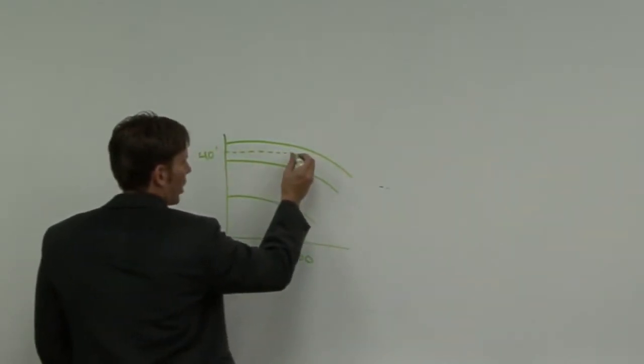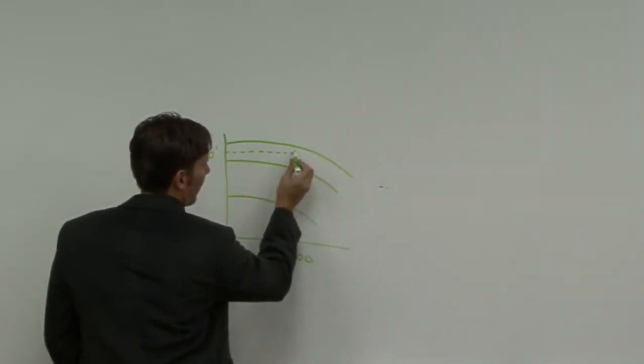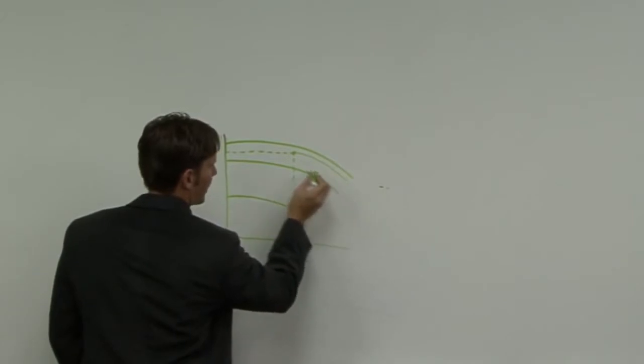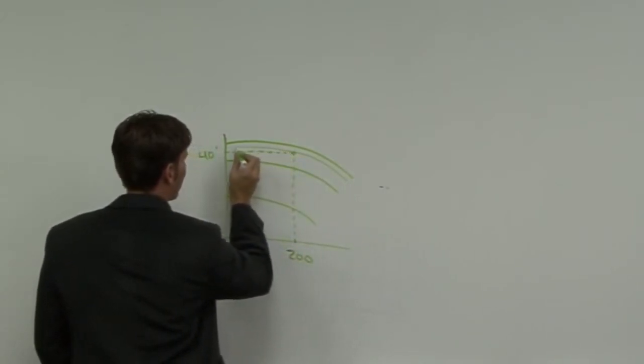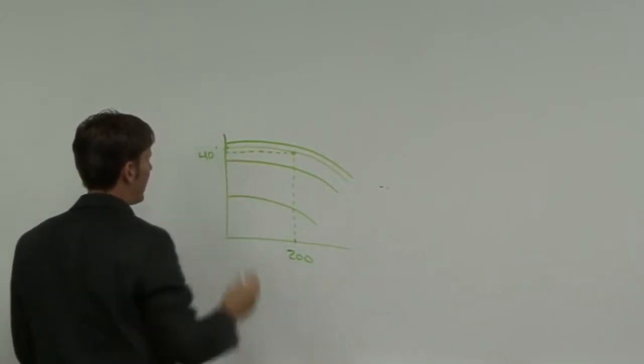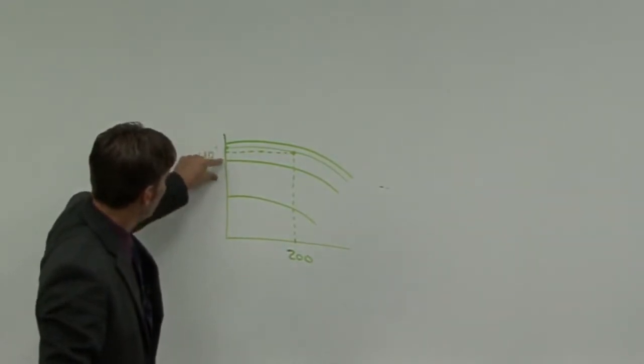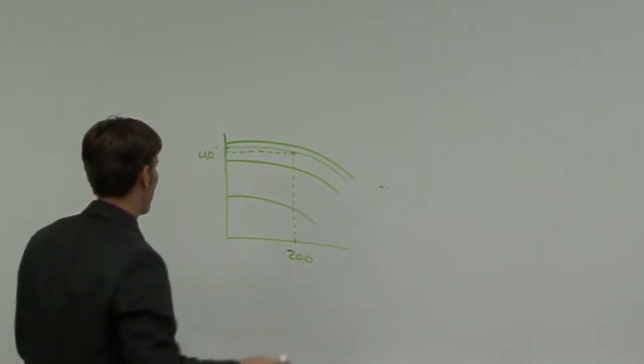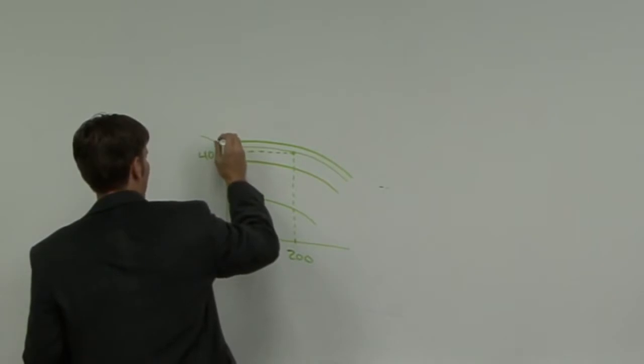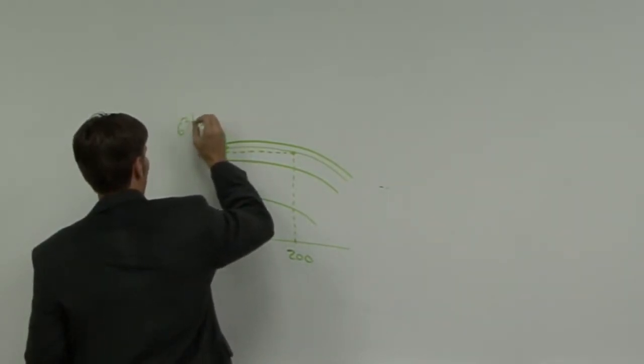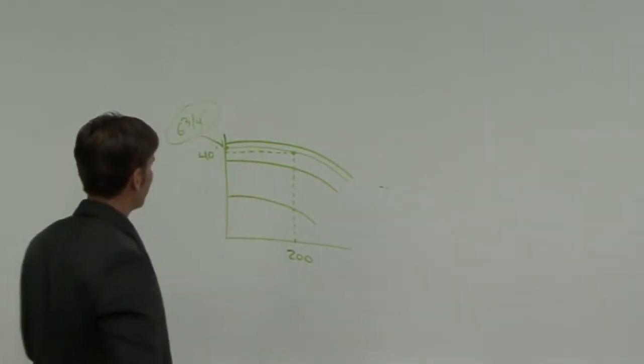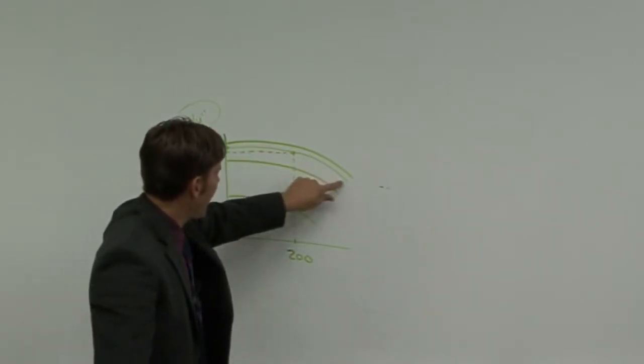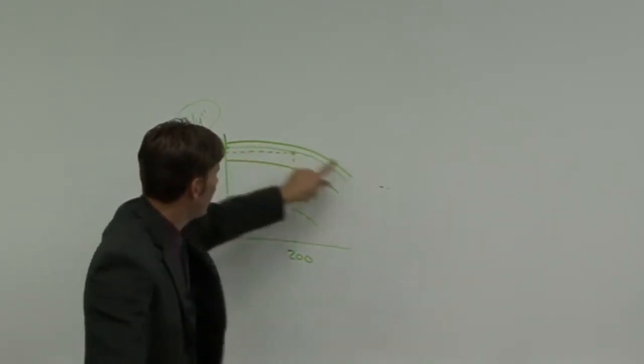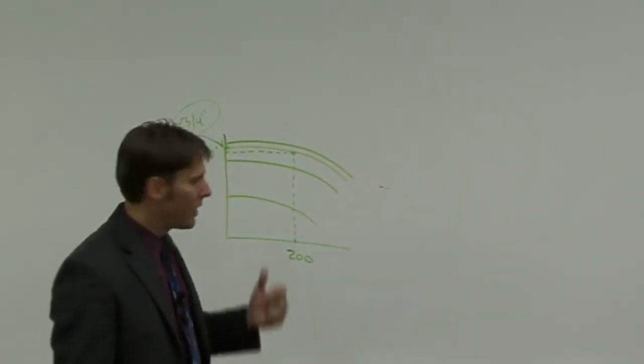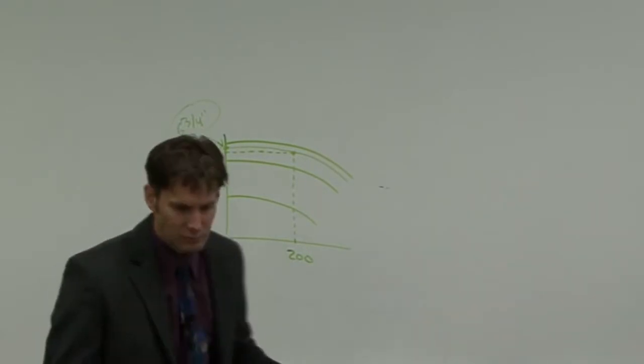So we could then look at this point and we could follow the same characteristics of these other curves, and right where we intersect here would tell us what our trim would be. And so we're just going to say that we are 6 3/4 inch trim. So that's what we would get. And now we're going to operate on this curve, not these other curves. So that's how we would look at that pump curve.